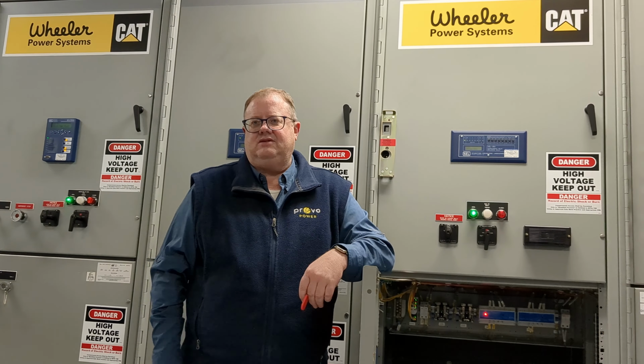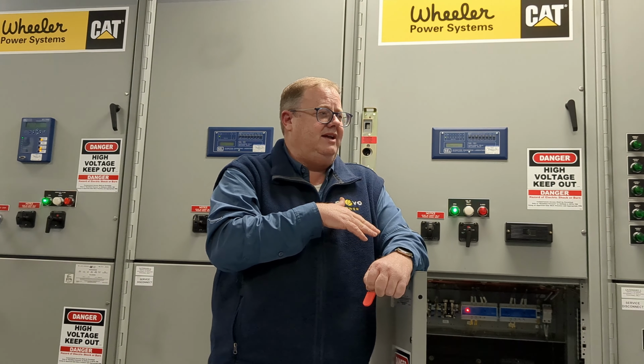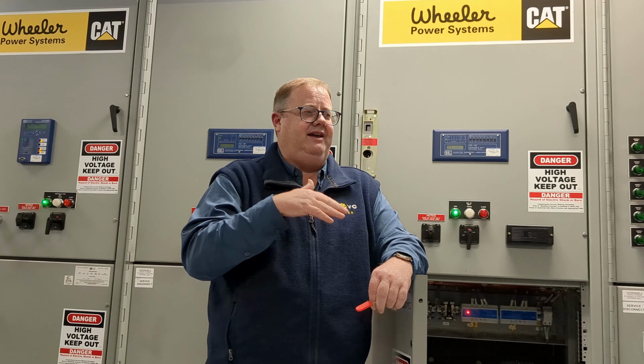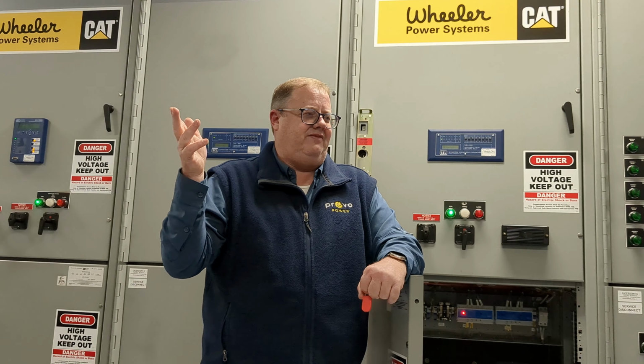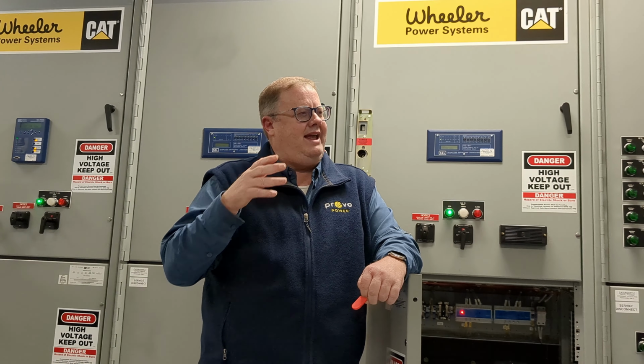And so you have to do fault studies, you have to know what the impedance is of your line, you have to know what the fault current is available out on your system, and then you coordinate those actions. The first time you open up the breaker, you're hoping the tree limb opens up, goes away. Whatever gets in the line that's causing the fault, you hope is cleared on the first one. And I think if you looked at engineering studies, 80% of the faults are temporary in nature.